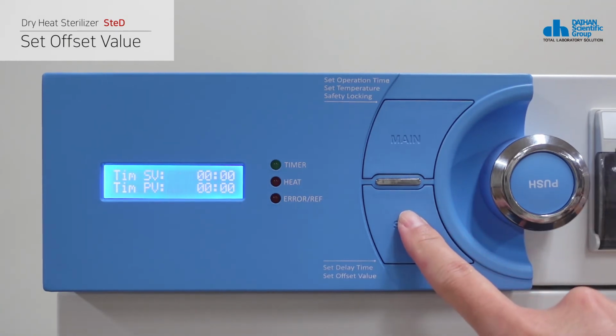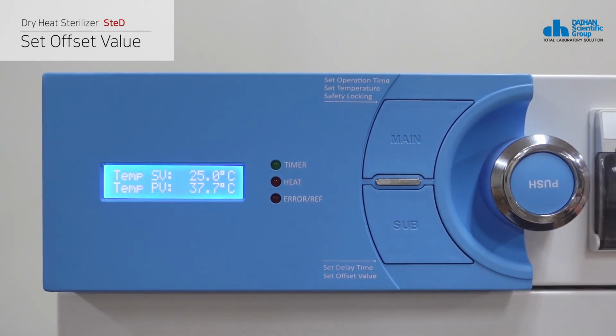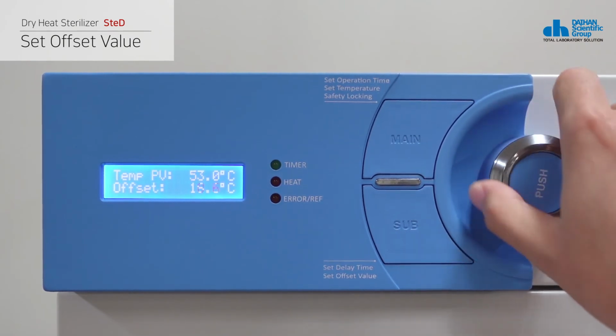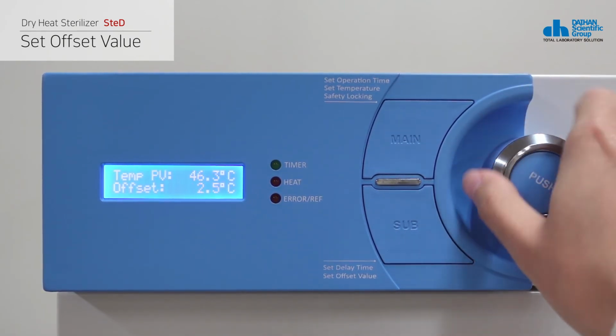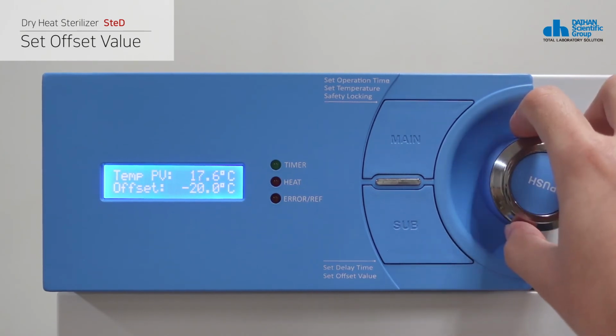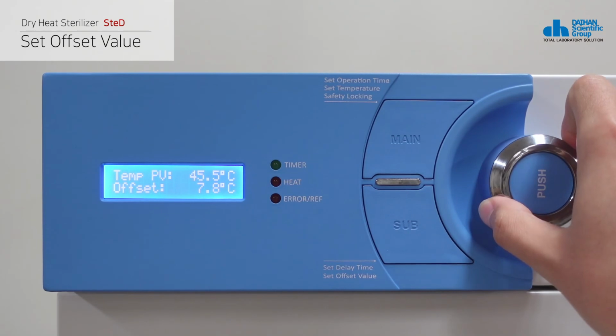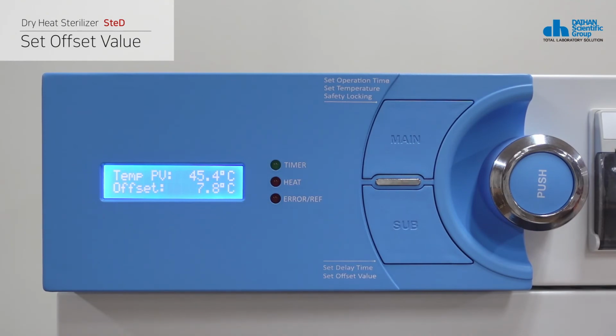Press the main button and the push button simultaneously on the temperature settings screen to enter the temperature calibration mode. The temperature correction function is used to match the thermometer you are using as a reference for the experiment with the thermometer displayed on this regulator. It is a function that allows you to set a calibration value to decrease or add to a certain value. The calibration value ranges from -20 degrees Celsius to 20 degrees Celsius and can be adjusted in units of 1 degree Celsius. After the calibration value is set, the current temperature is displayed including the calibration value.